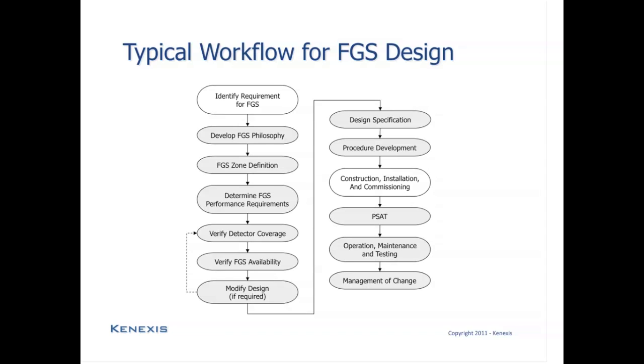Now, if either the detector coverage targets or the safety availability targets are not achieved, then we will go back and modify the initial fire and gas system design as specified by a fire and gas system expert using their heuristics for placement. Then you're going to need to go back and change the design, looking at the coverage maps and looking at the availability calculations to determine where the weak points are and rearranging your detector placements and other attributes such as redundancy and test intervals, and even the type of equipment that you're employing in order to improve your coverage or availability, whichever did not achieve the target design, and then rerun your verification calculations. And this process, again, is going to occur recursively until the performance targets have been achieved.